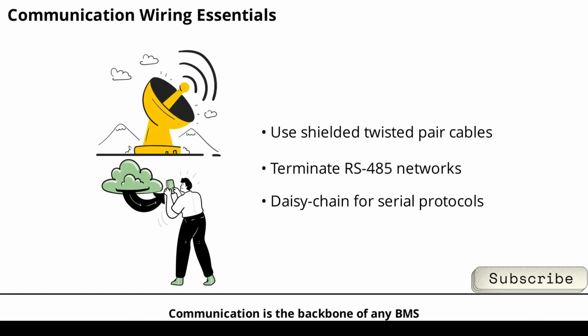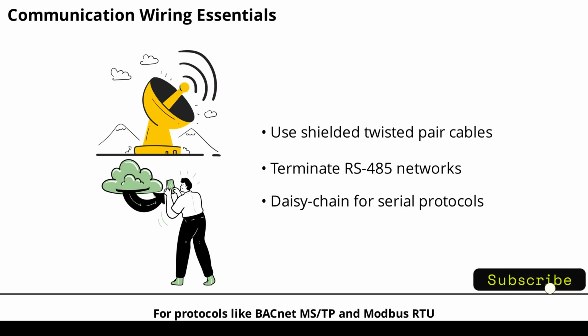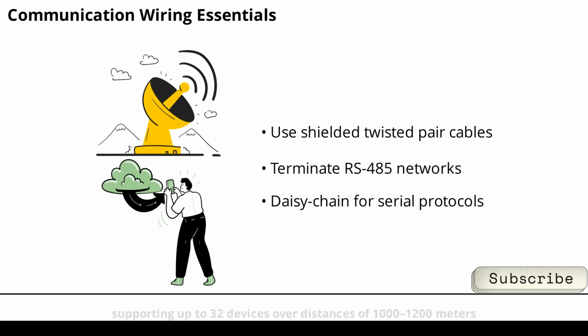Communication is the backbone of any BMS. For protocols like BACnet MS/TP and Modbus RTU, use shielded twisted pair cables, supporting up to 32 devices over distances of 1,000 to 1,200 meters. For BACnet IP, Cat5e or Cat6 Ethernet cables are standard, with network distance determined by switch design. Always terminate RS485 networks at both ends, set the correct baud rate, and use daisy chain topology for serial connections. Proper communication wiring ensures fast, reliable data exchange between controllers and the BMS server.